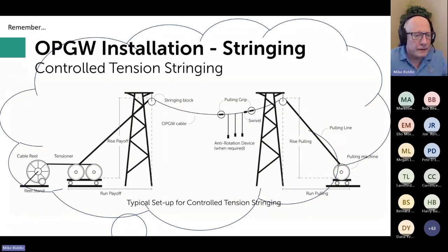The only other thing you can do at that point, if you know it's a great reel stand and there's not a problem with the axle and the brake is turned off, then what you're probably dealing with is a very long pull. And the only thing you can do there is go slow until enough of the cable has depleted so that the reel is rotating more freely. So that's the best I can do in that situation.